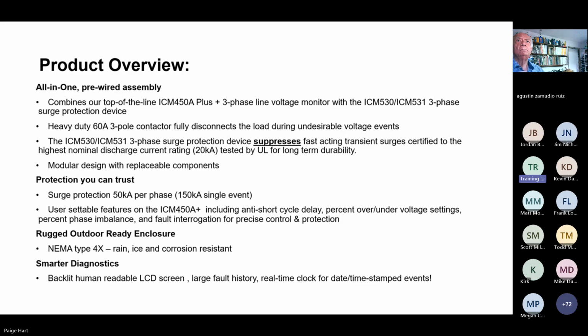We supply this with a heavy duty 60 amp 3-pole contactor, which fully disconnects the load. And we picked that range because that covers a pretty wide range of applications, for both 208 and 240 and 480 volt three-phase services.